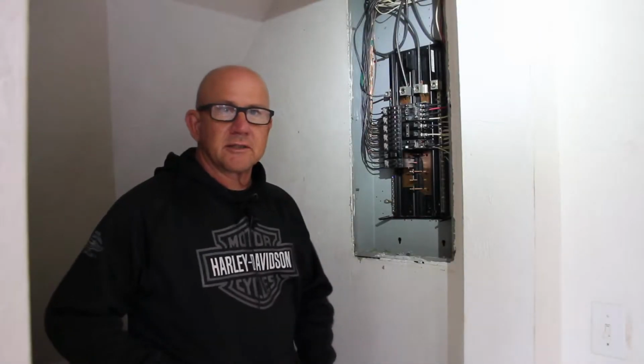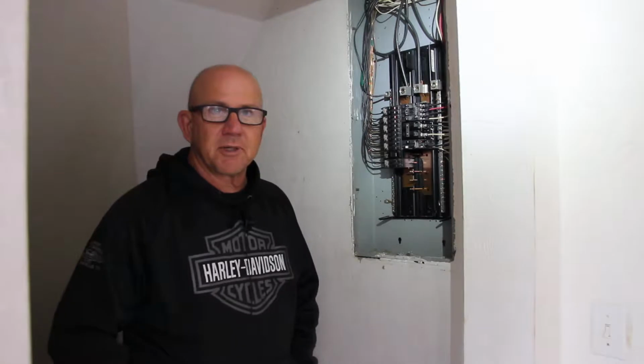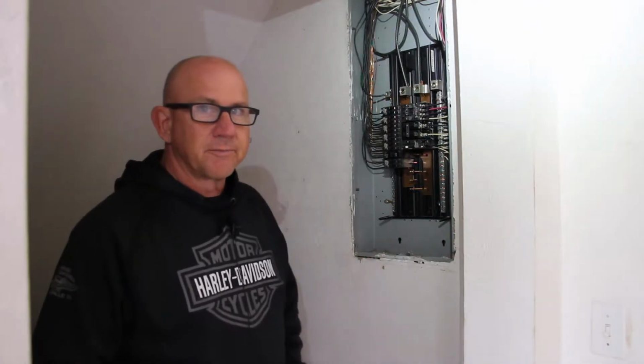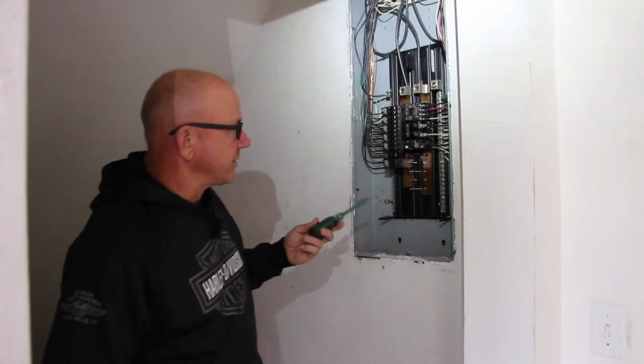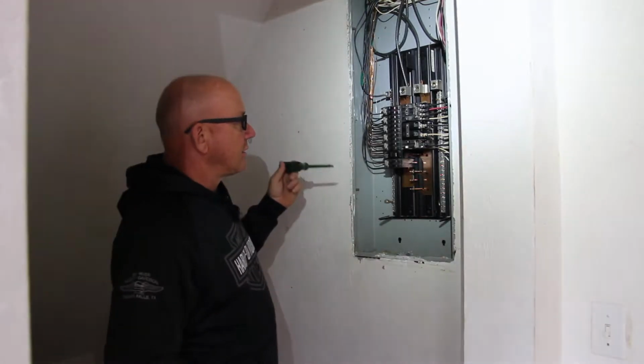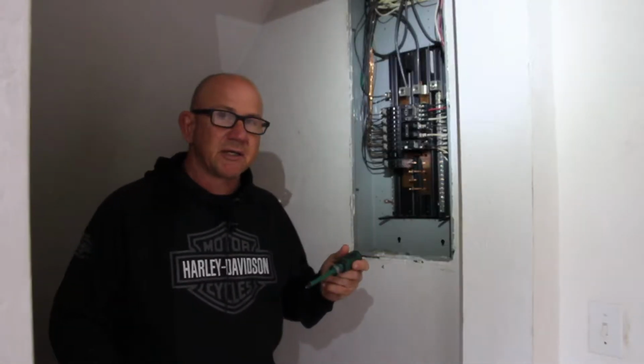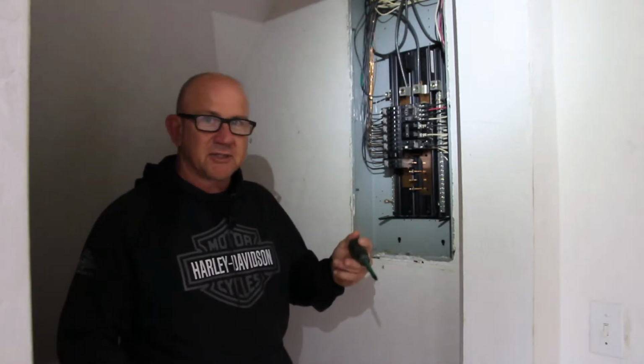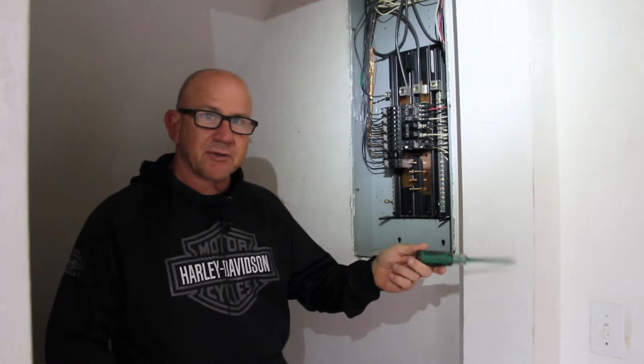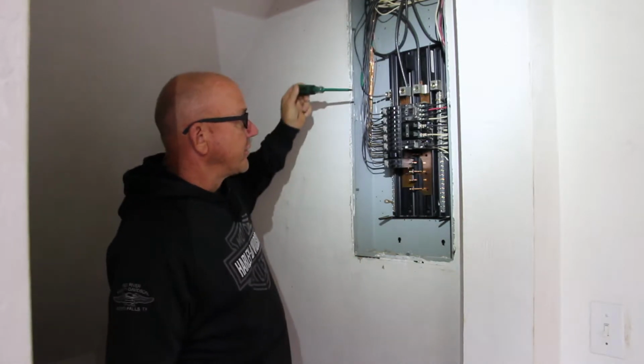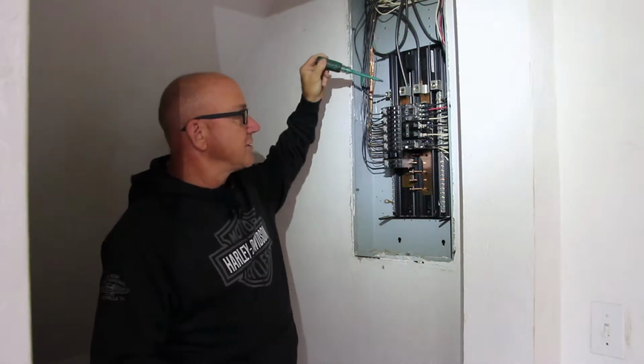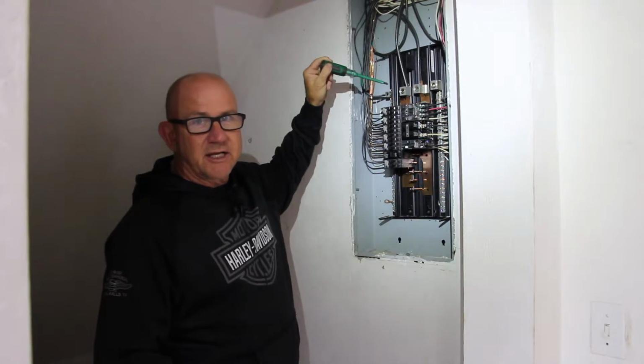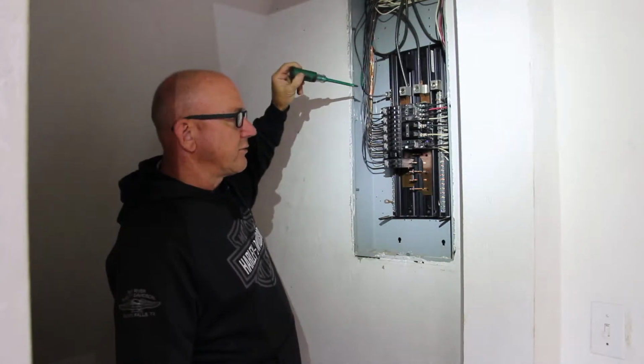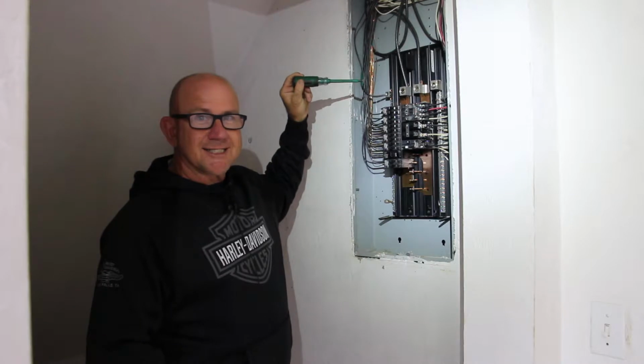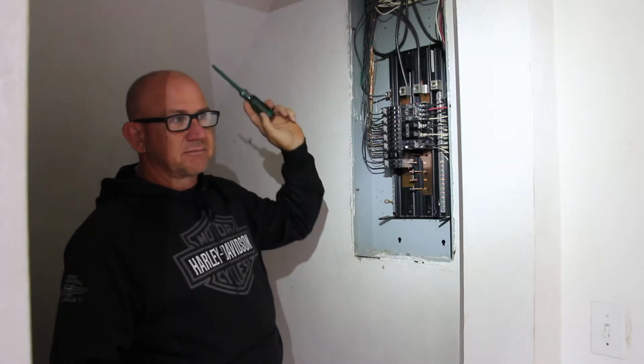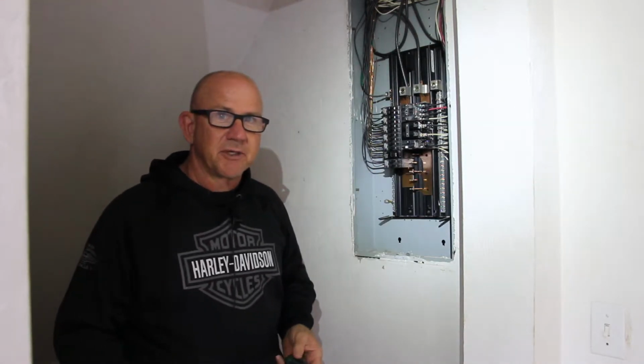Hello, here we're at the secondary service panel on the same property that we looked at a little earlier. We're going to be identifying some issues here. First off, this is a secondary panel. It's fed from a circuit breaker in the main distribution panel that we looked at earlier. One of the main problems we find here is there's no disconnect for this panel. The other panel is not within sight, and it's at least 30 to 50 feet away from here.